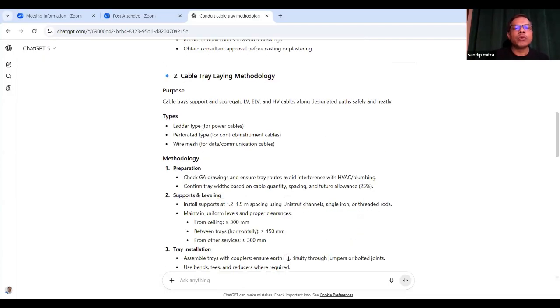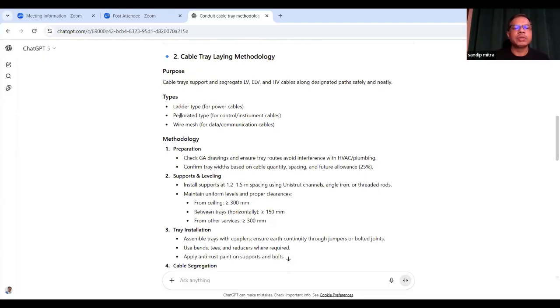In the same way, you have to follow the methodology for how to lay cable tray. The purpose of the cable tray is to support and segregate LV, ELV, or high voltage cables along designated paths, safely and neatly. Different types of cable tray are available. There is the ladder type, mostly used for power cables. Perforated type we use for control and instrument cables. Wire mesh for data and communication cables.